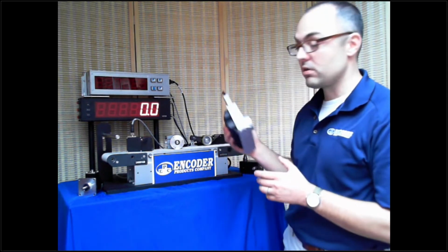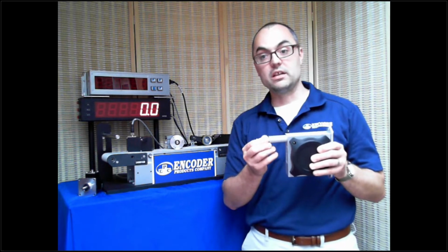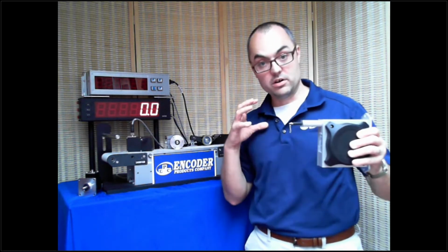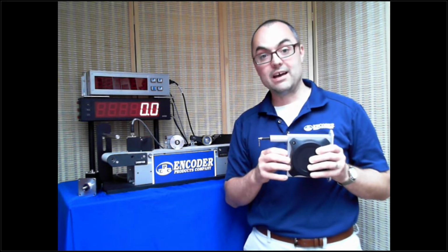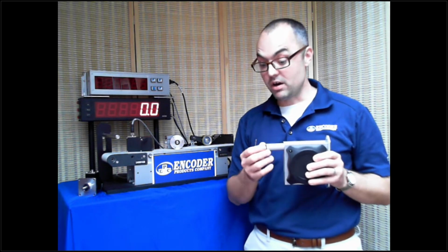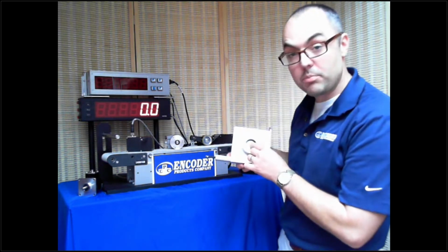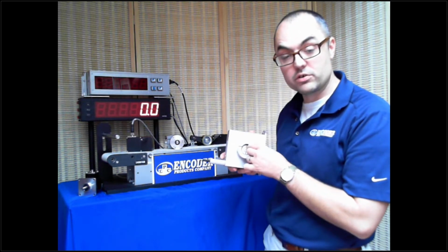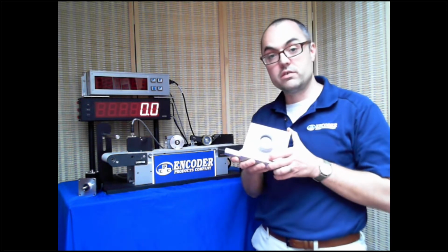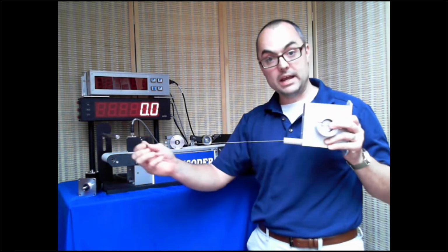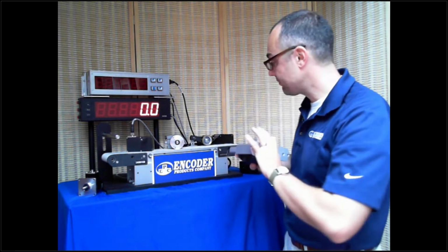A draw wire encoder eliminates the need for an expensive scale, even over long distances. This draw wire itself, in its largest model, can go to 42.5 meters. That's pretty far, and you're not investing for that length of scale. Because of the hard coupling of the drum to the encoder, there's no backlash in here. So you can repeatedly measure that linear distance over and over, back and forth, as you could with a scale.